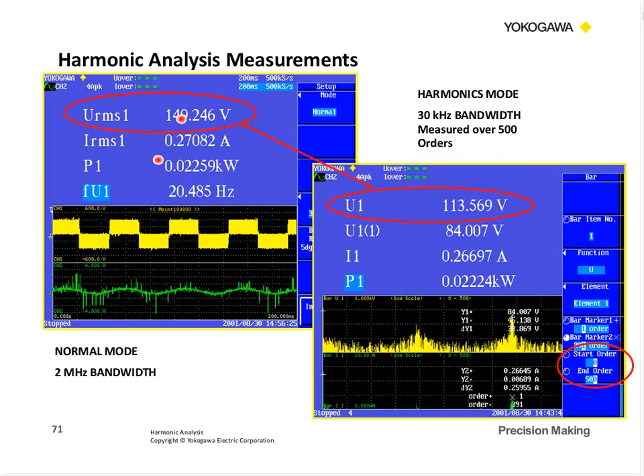Now this is where we talked about the bandwidth of the instrument. Here's one where we had the bandwidth capability out to 2 megahertz, and look at that RMS voltage on this PWM, 149. Now here we're in the harmonic mode, and in the harmonic mode, it was limited to 500 orders, or in this case, 30 kilohertz. So we're only able to look at this voltage up to 30 kilohertz. And you'll see we select the harmonic order, the starting and ending, and it ended at 500 orders. You'll see this does not say RMS; it just says U for voltage. So it's not a true RMS measurement. So you've got to understand how your instruments are working.